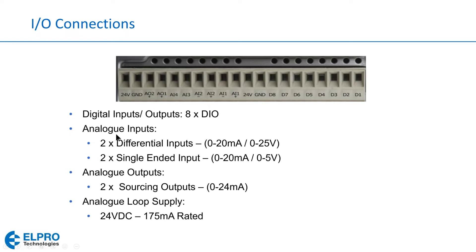We have four 4-to-20 milliamp inputs. Two are differential type and two are single-ended. The single-ended inputs refer to ground as the negative terminal for all inputs. The differential inputs have both a plus and a minus — AI1 plus and AI1 minus, then AI2 plus and AI2 minus — where you wire the 4-to-20 milliamp positive and negative connections. AI3 and AI4 are single-ended. I have another diagram in the next slide that clarifies what is meant by single-ended and differential inputs.